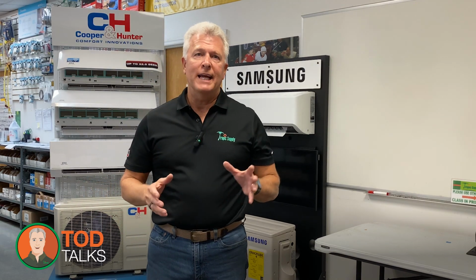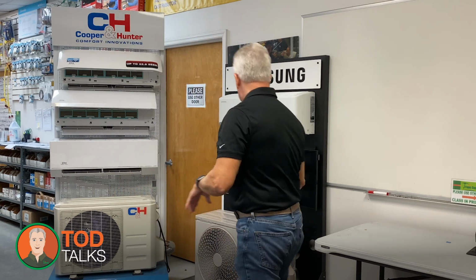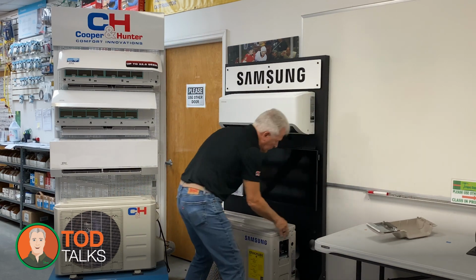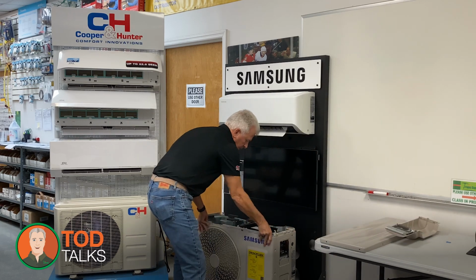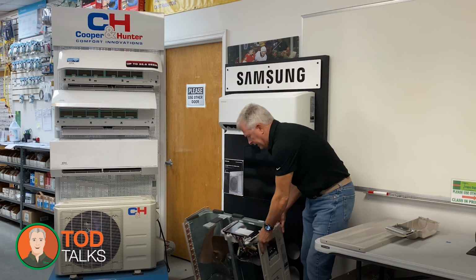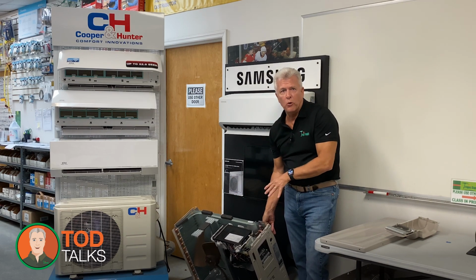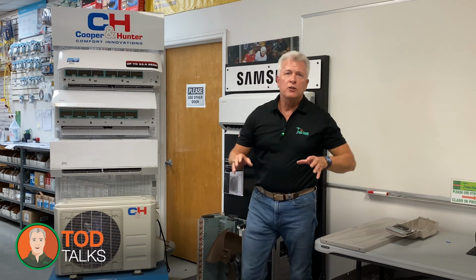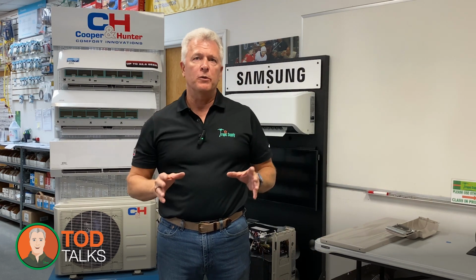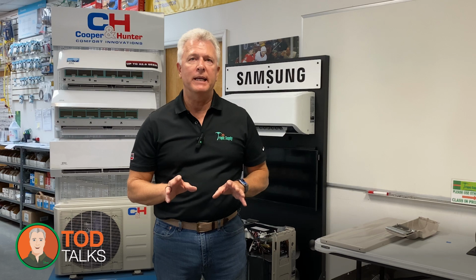Mini splits have a bit of a reputation for looking different and operating in ways that aren't quite like traditional systems. When you first open one up, there's not much inside, just a control board and a bunch of sensors. Unlike your typical split systems, these units use inverter-driven motors, meaning they don't just turn on and off at full speed. Instead, they ramp up and down to meet the demand, giving you smoother operation and better energy efficiency. It's all thanks to a bit of DC magic that keeps things running efficiently and quietly.